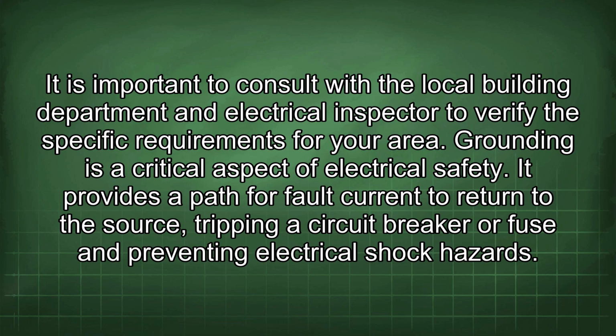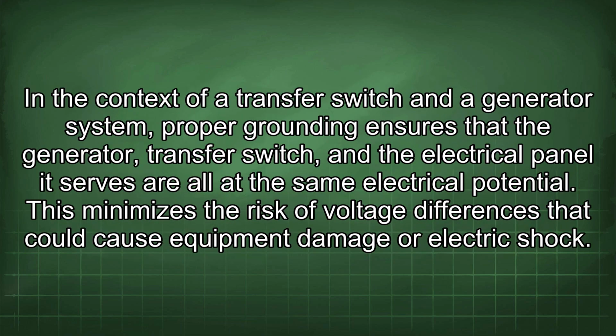It provides a path for fault current to return to the source, tripping a circuit breaker or fuse and preventing electrical shock hazards. In the context of a transfer switch and a generator system, proper grounding ensures that the generator, transfer switch, and the electrical panel it serves are all at the same electrical potential. This minimizes the risk of voltage differences that could cause equipment damage or electric shock.